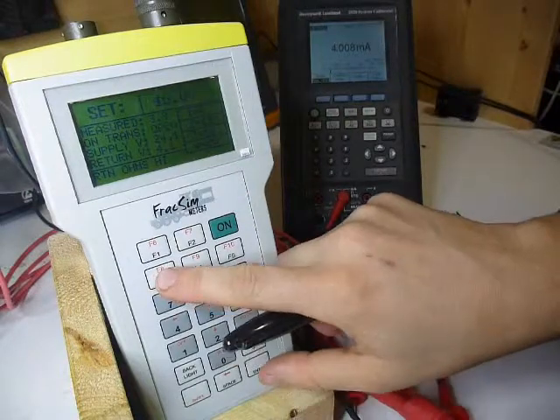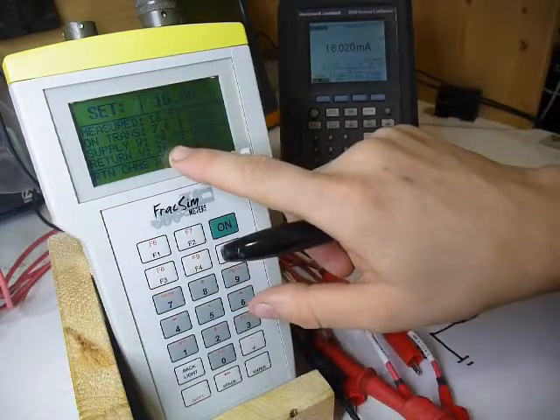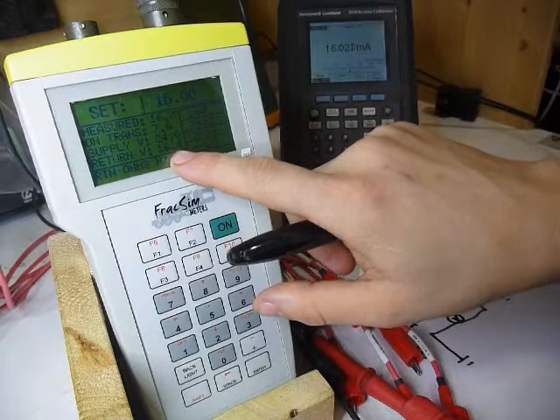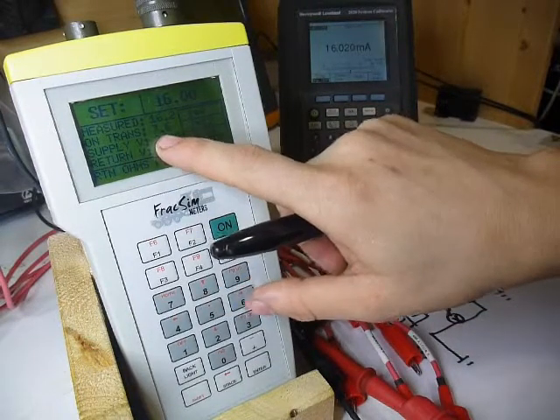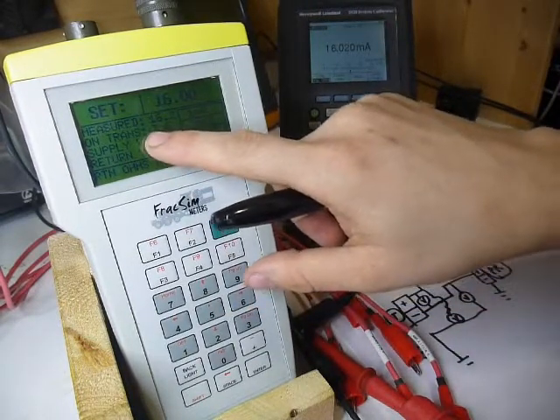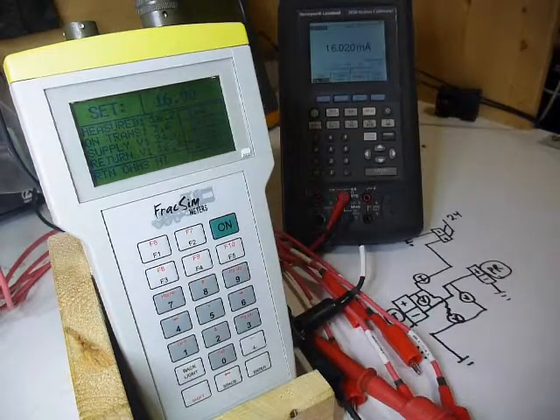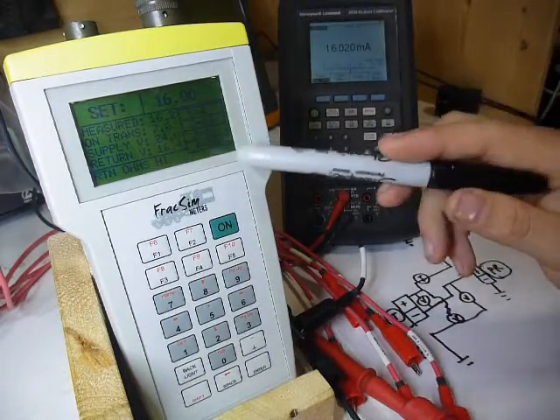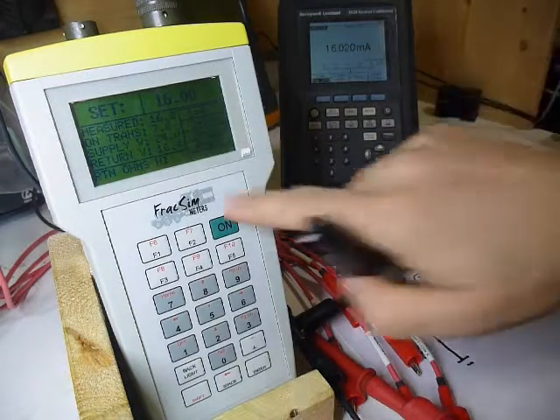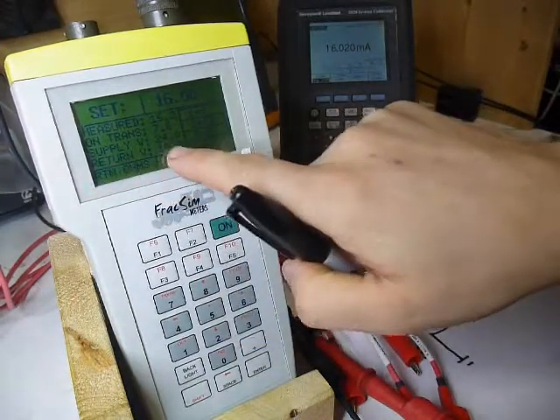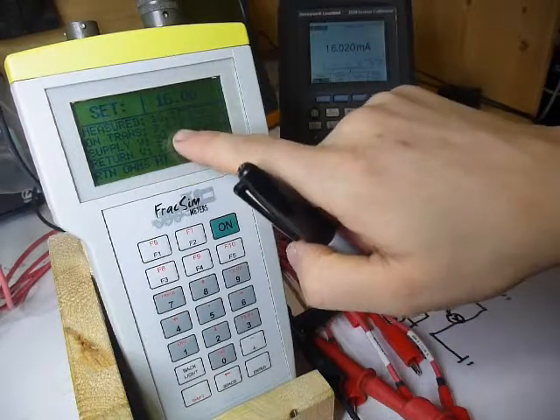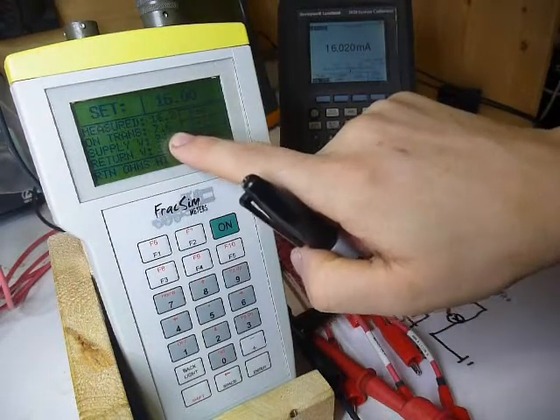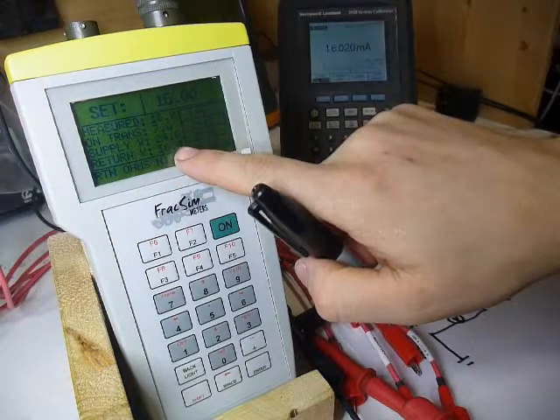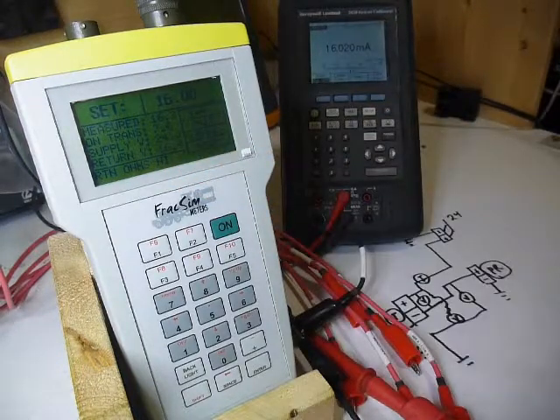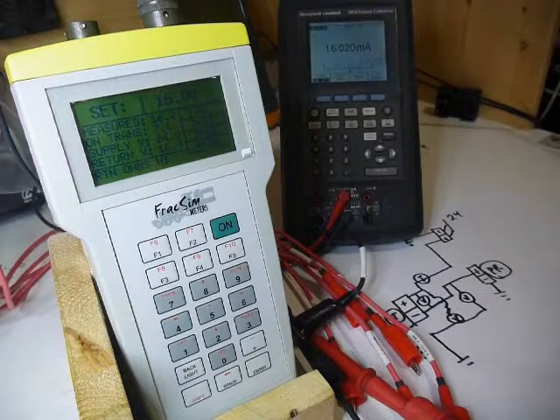So if I were to try something like 16 milliamps, we're actually dropping 16 volts on the return, and we now only have 7 volts on the transmitter. And most transmitters will not operate correctly at 7 volts. So you can see from this information, you have return ohms high for one, but you can see it because the return voltage is very high. You can see that your transmitter now has only 8 volts on it. So you can tell right away that the problem is on the return side. So this system is useful for more advanced diagnosing of current loop issues.